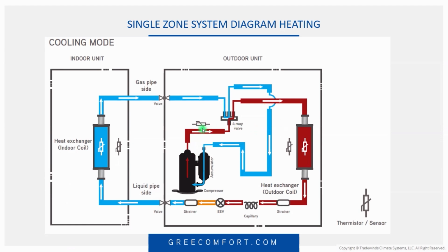with one exception to that rule. If that thermistor is on the discharge line of that compressor, it is going to be a 50K thermistor. Why? Because that is the hottest pipe in the entire machine. A 20K thermistor is not going to work in that application. That's why they're using a 50K thermistor. So, moving on.